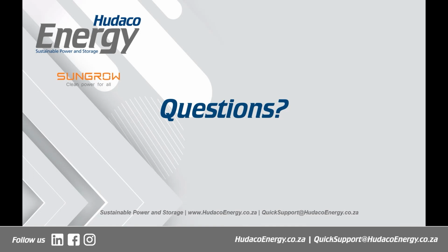While we're on that as well, one of the things I didn't discuss, and this is really, really important for South Africa. Sorry. One other thing, there is a setting in the inverter where you can set active power. So you could set active power to say 50%, and then it'd only be a 3 kilowatt maximum output on active power. And yes, it is password protected in the sense that you would give the client access to the portal, but he would only have limited access. The actual installer would have a higher priority with being able to set certain settings. So yes, you can restrict the inverter to only output a certain amount. Great. Thanks very much. I really appreciate it.